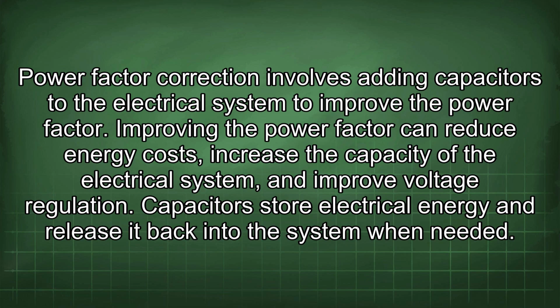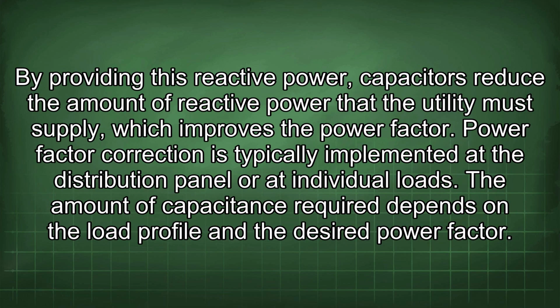Capacitors store electrical energy and release it back into the system when needed. By providing this reactive power, capacitors reduce the amount of reactive power that the utility must supply, which improves the power factor. Power factor correction is typically implemented at the distribution panel or at individual loads. The amount of capacitance required depends on the load profile and the desired power factor.